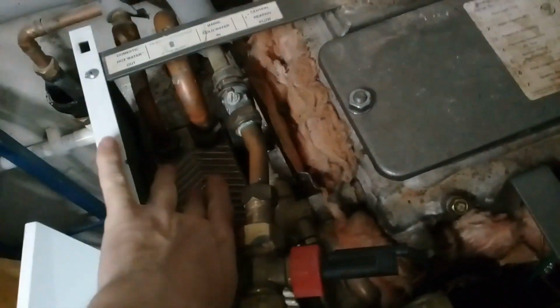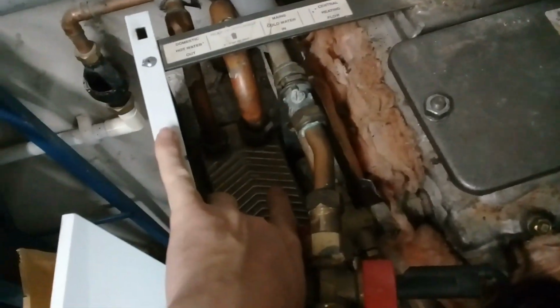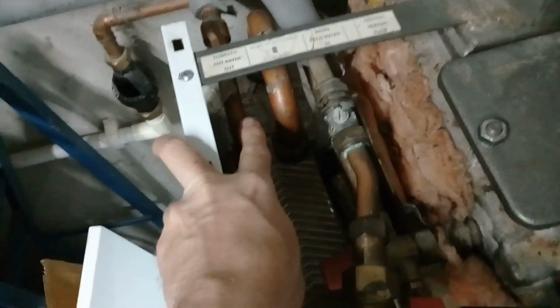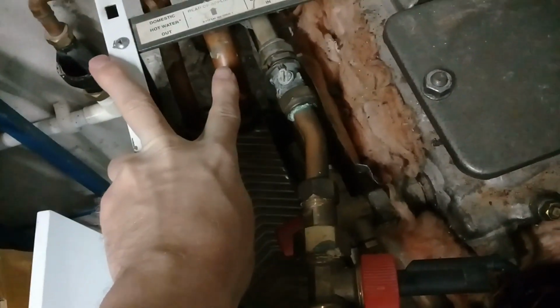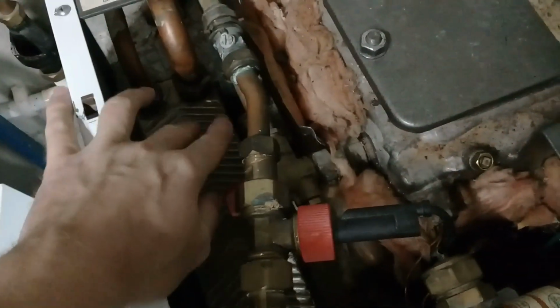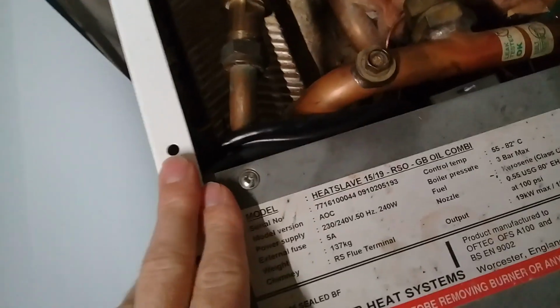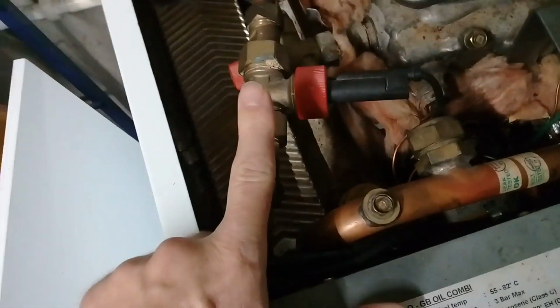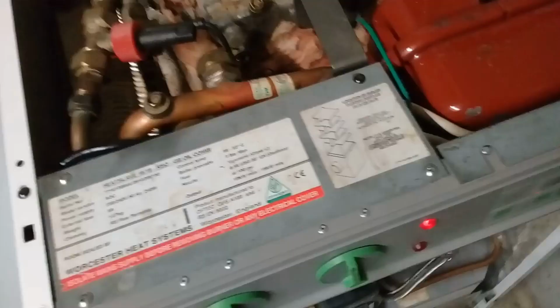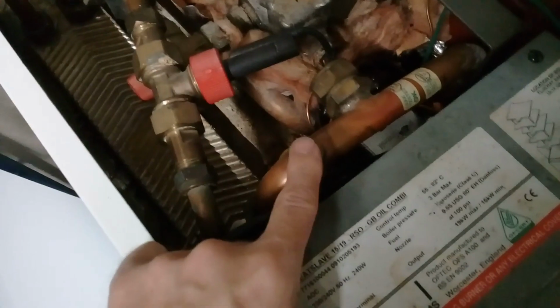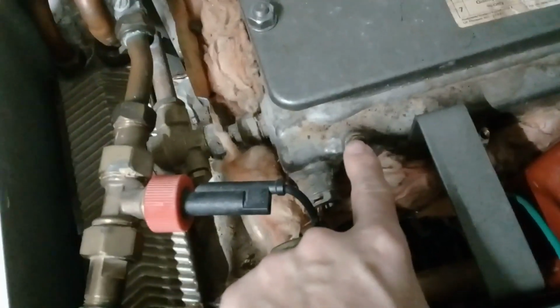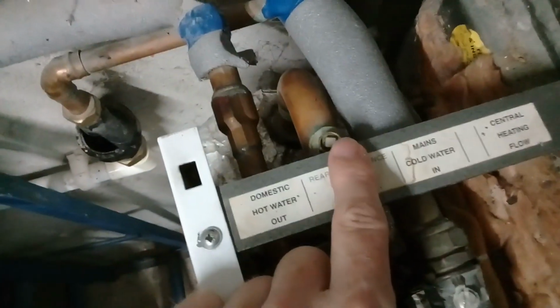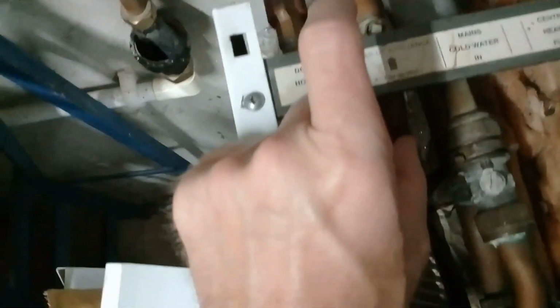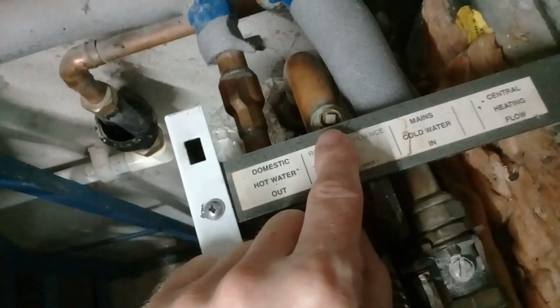So this is the plate heat exchanger that does the hot water. So we've got the hot water coming out. We've got this pipe that's feeding the hot water from the boiler system through the heat exchanger. And then we've got the flow switch there. So that's the cold water in this flow switch. A couple of other things that are worth pointing out. Bleed valves. This one here for the hot water. This one here, top of the boiler. This one here for the heating of the hot water.